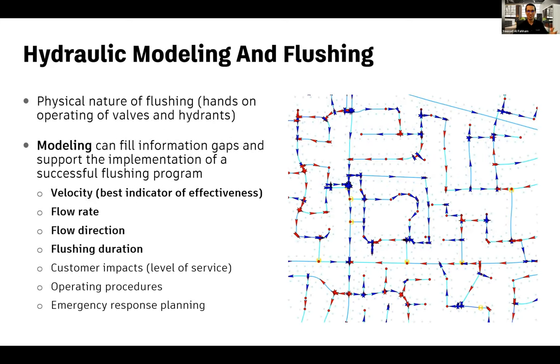Where does hydraulic modeling fit in this very physical flushing world? Modeling can help you fill information gaps to support the implementation of your flushing program. Key metrics that can make or break your flushing program include hitting target velocities, the right flow rates, and the correct flushing durations in order to clean your areas correctly. With a model, you don't need to assume — you can verify as you're closing valves and creating sequences that you're meeting your velocity, flow direction, flushing duration, and flow rate requirements.